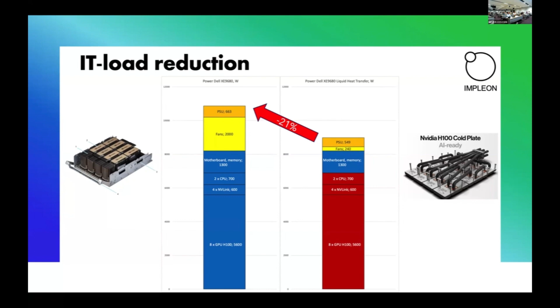Here I show the components of the server. The yellow one is the fans' energy consumption in the air-cooled version, and orange is the power supply unit. So when you shift to liquid cooling, you reduce the energy consumption of the fans, because the red components - GPU, NVLinks, and CPU - are liquid cooled, and the rest is air cooled. This is why energy consumption of the fans is heavily reduced, and that makes an impact also on the power supply unit's energy consumption. This is why we get a 20% reduction. So just the way of cooling the IT equipment makes an impact on its energy consumption.